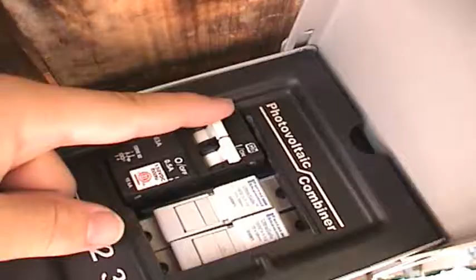Now, in order to disconnect the solar panels from the rest of the system, we simply need to flip the switch on the GFP device to the off position. Now our solar panels are disconnected from the rest of the system, and we can go ahead and fix the outdoor cable. Once the cable has been fixed, you can go ahead and flip the switch on the GFP device back to the on position.